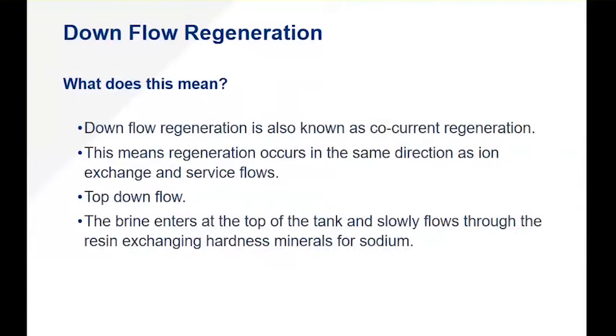The first step — let's define downflow regeneration first. Downflow regeneration is also known as co-current. This means the regeneration occurs in the same flow path as the ion exchange and service flows — that means top down, from the top of the tank down. The brine enters at the top of the tank, slowly flows through and over the media, pushing off the hardness minerals and replacing them with sodium. It's the opposite of the softening process. This flow path of downflow regeneration determines the order of the steps and what we must do first.